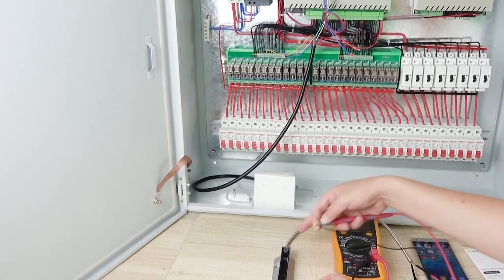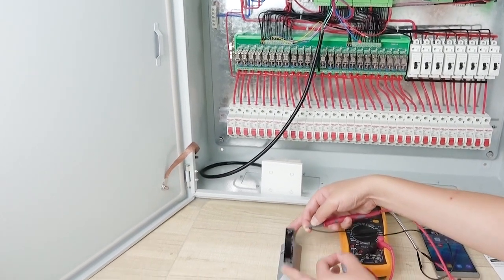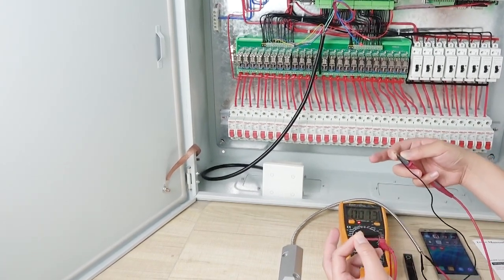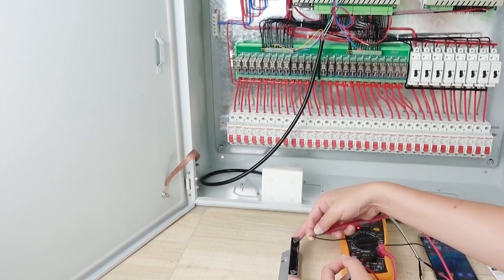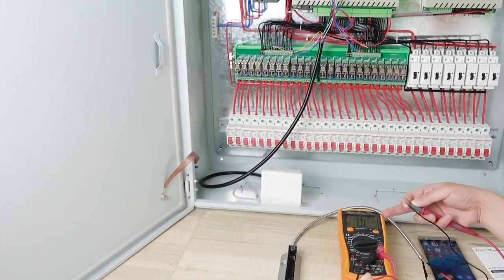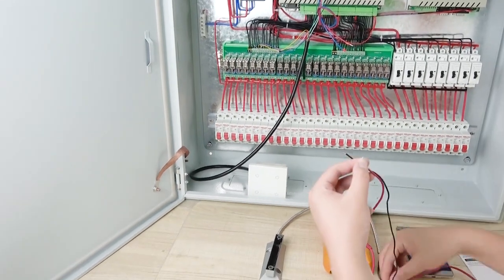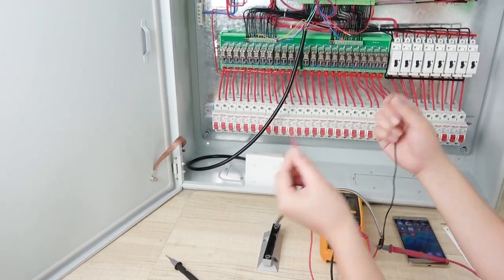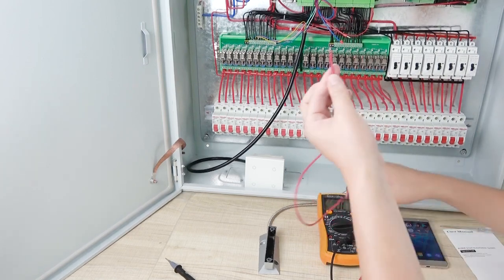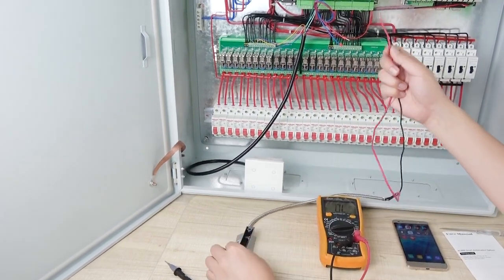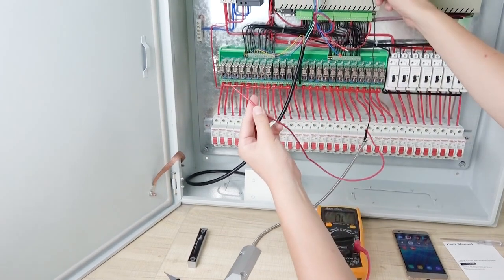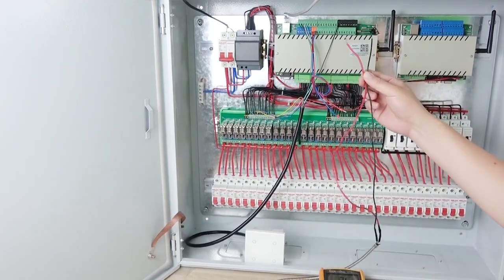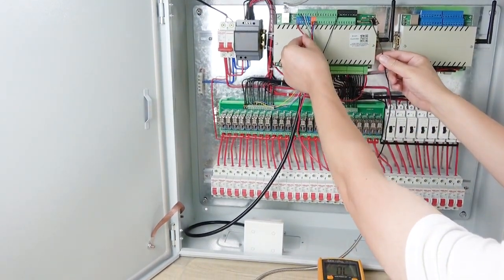And if we open the door, just like this, remove this body, you can see the LED is on, and the meter has a sound when the door is closed. When it is open, you can see the sound does not appear. So this just outputs a dry contact signal, just open and close, open and close. So we can use this very easy signal type. We can just connect the two lines to this ground and this digital input. Because we are using this one sensor, I choose to use digital input 1, and this is the ground.